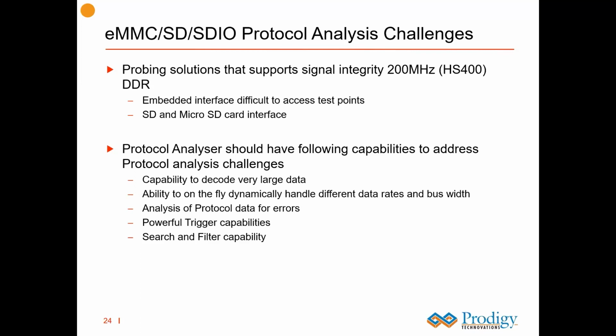Okay. And you should also like to see on-the-fly decoding and dynamically change the data, because your data rate can vary from 25 megahertz to 50 megahertz, 50 megahertz to 200 megahertz. So the data rate keeps changing, and we need to keep track of the data rate changes and capture the protocol activity. Similarly, bus width can vary from 1 bit to 4 bit to 8 bit. Again, we need to track that and capture that. And analysis of the protocol data for errors: we have to check on the fly for any errors, because if you captured a few gigabytes of data with millions of commands and responses and you have to manually go and find those errors, it can be very, very complicated and stressful.